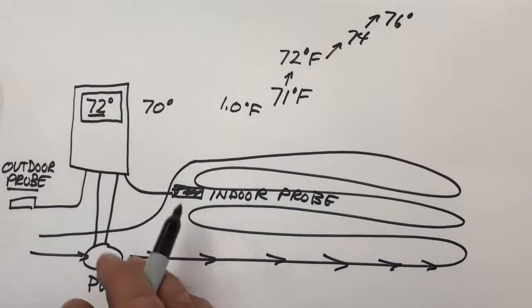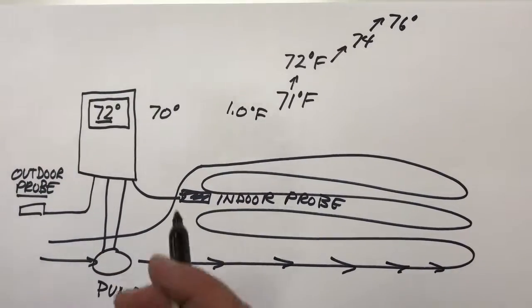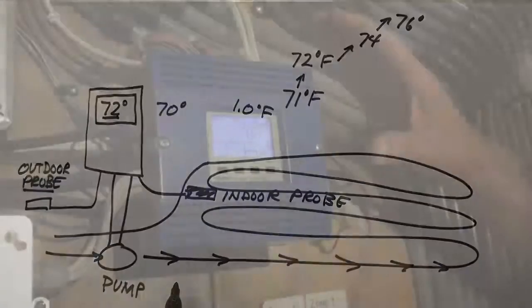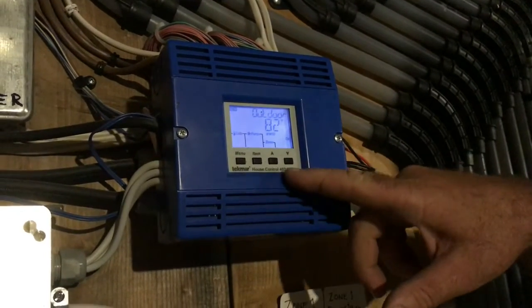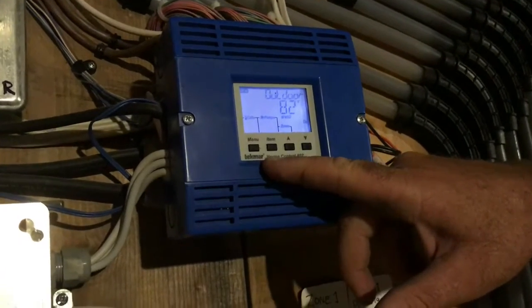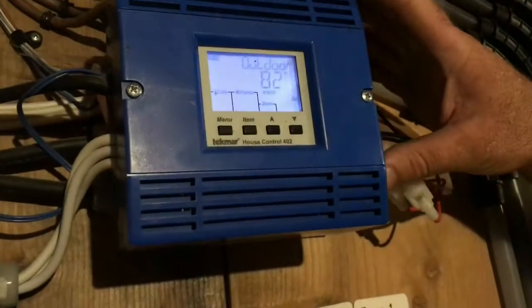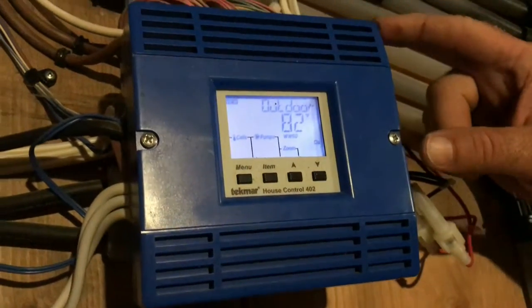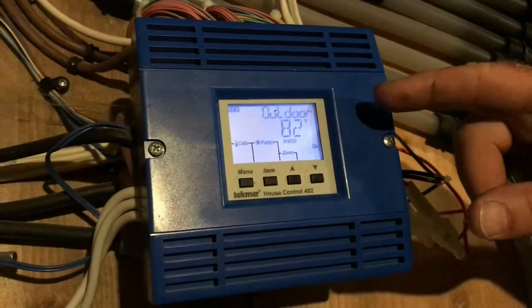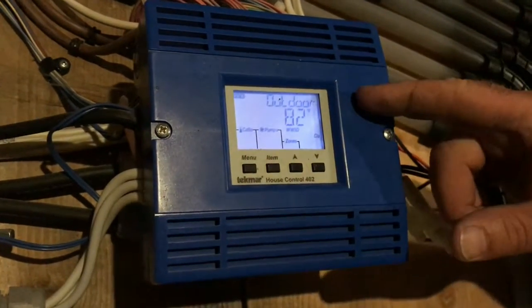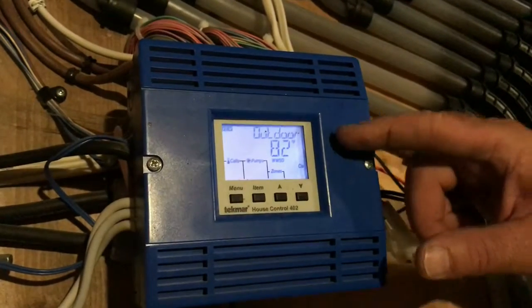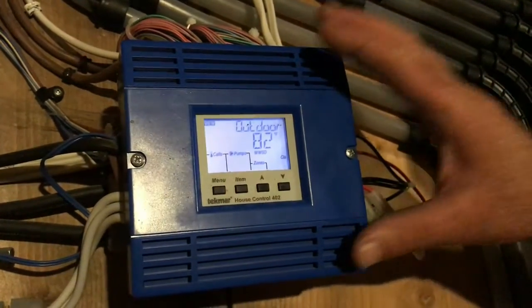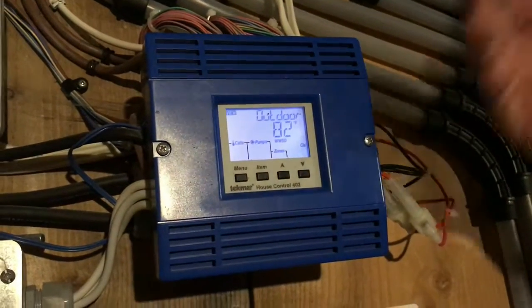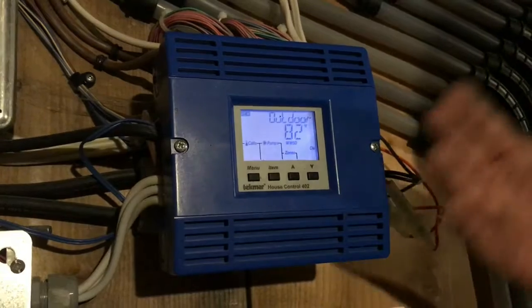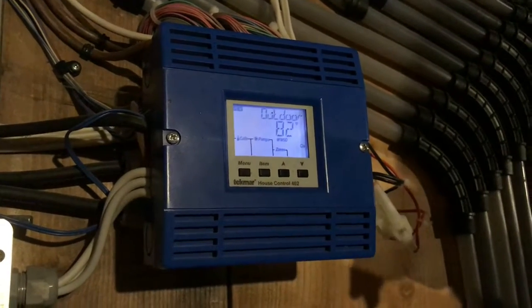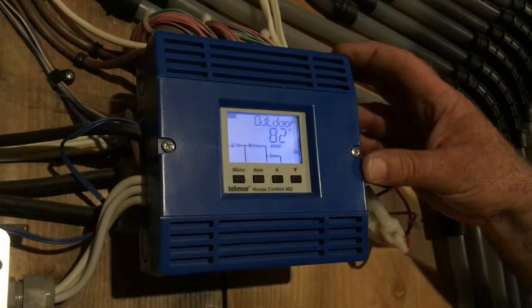So let me take you to an installation I've done and just show you what the equipment looks like after it's installed. So this is a smart thermostat system, or at least the central brain of it. It's made by a company called tekmar. They're a company that makes all kinds of smart stuff like this. The thermostats around the house plug into this, and the outdoor temperature probe and the in-floor temperature probes also plug into this. And this is what decides the anticipation of the temperature and how much a given room will overshoot, how much it has to shut off before the set point in order that it doesn't overshoot the mark.